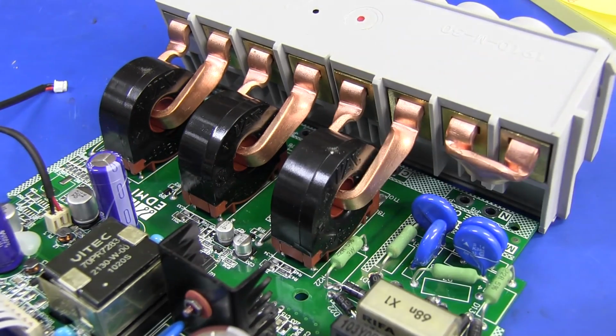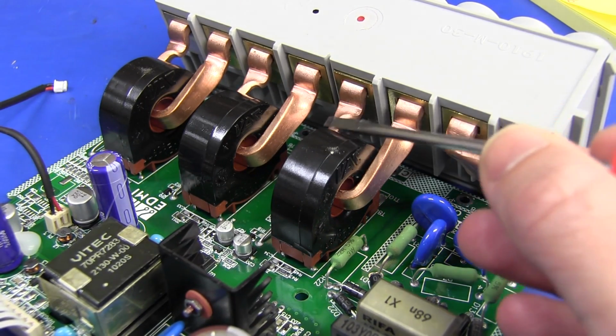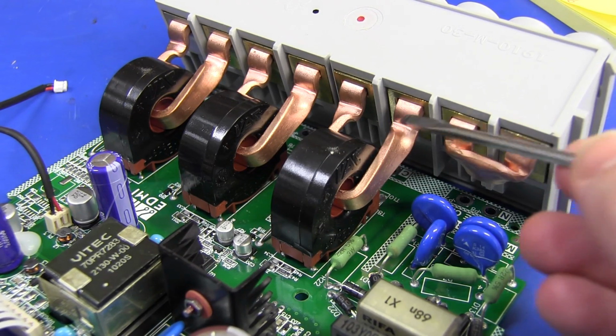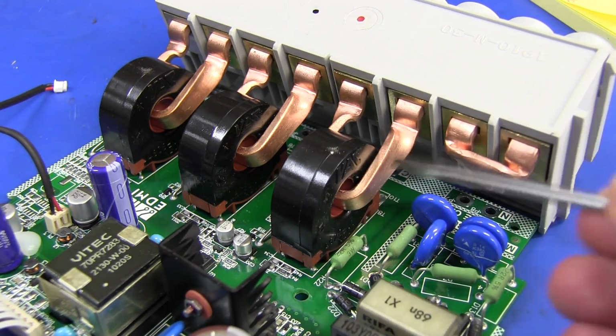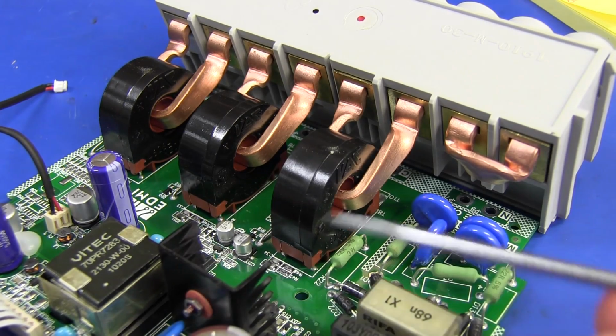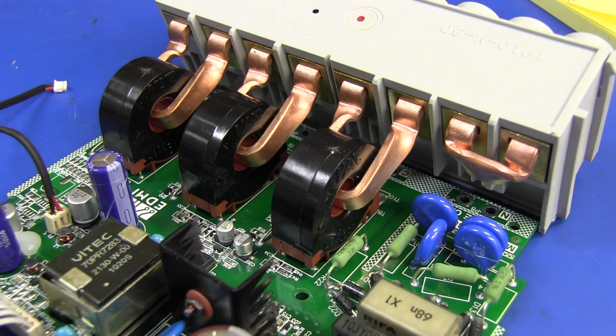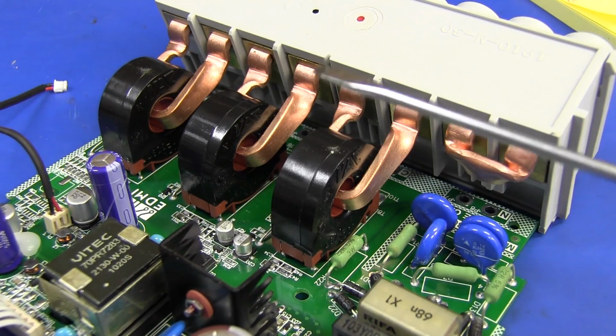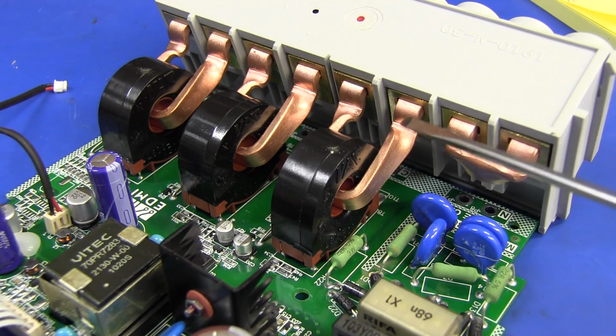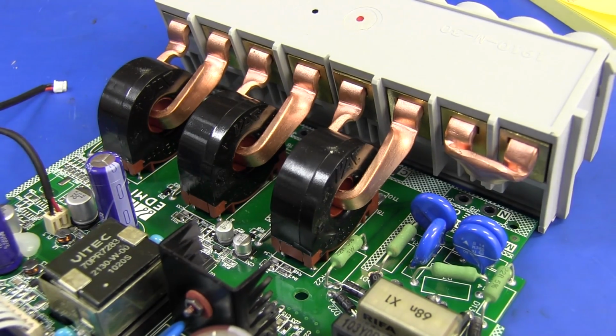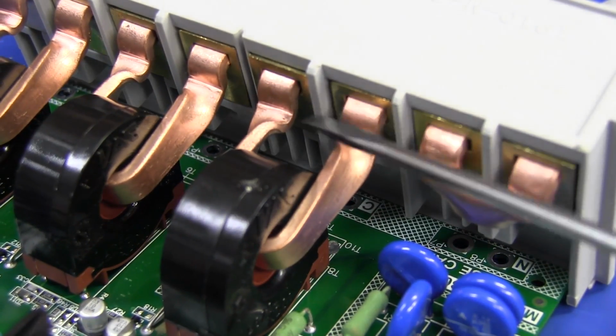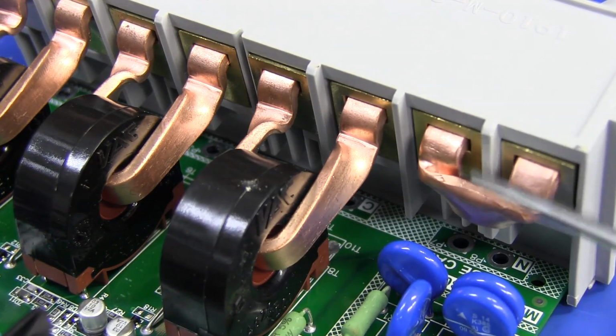The reason they've gone for these funky current transformers is that, as you can see, there's practically no power dissipation at all in this. It's basically only drawing the current it needs to drive the circuitry and measurement stuff, which isn't much compared to a traditional current shunt resistor. Look at these big bus bars, huge links down in here, they're absolutely massive. These are the 3 phases, and we've got our neutral.